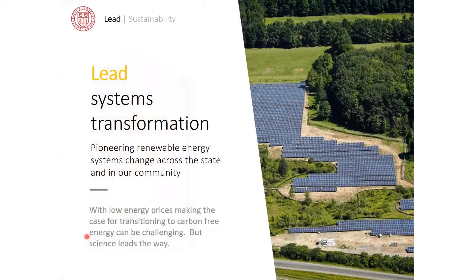For electricity, the technology is the easy part. The challenging part is policy — state tariffs, the Public Service Commission, working with utilities and integrating into their distribution systems. We currently have five 2-megawatt solar farms and six campus rooftop arrays totaling 100 kW — the equivalent of 7% of Ithaca campus power, which is the maximum possible under the current regulatory framework for distributed energy. Combined with our hydro plant, we're at about 10%. If the Dryden community solar farm comes online, that's another 18 megawatts — tripling our current renewables.